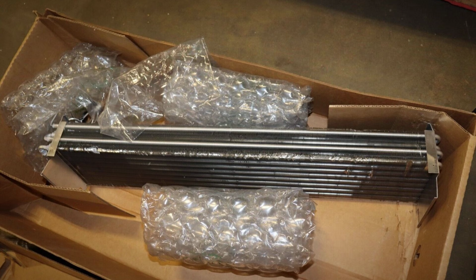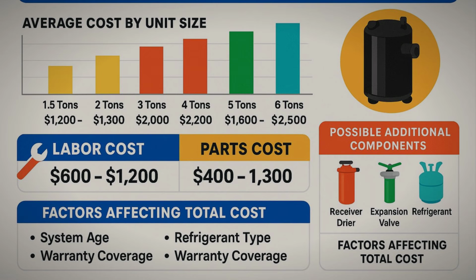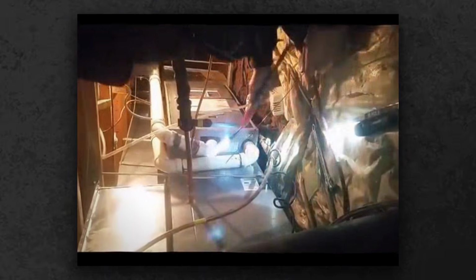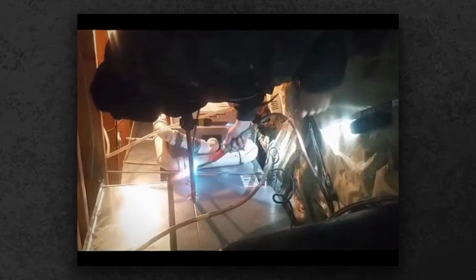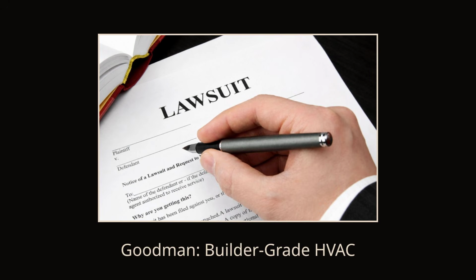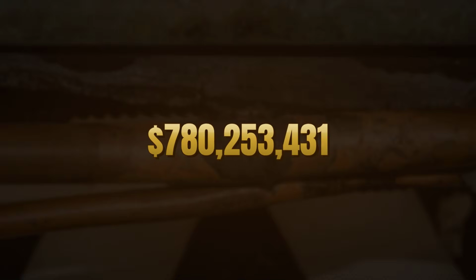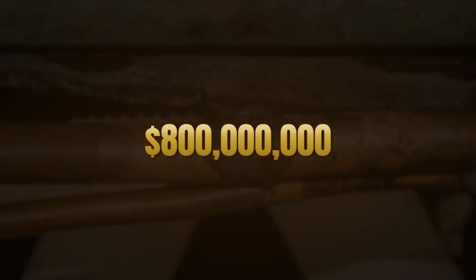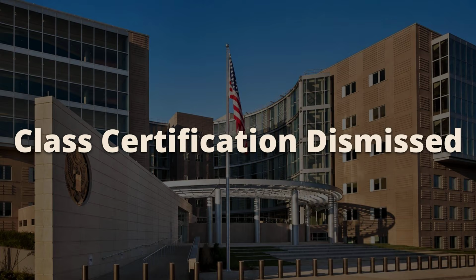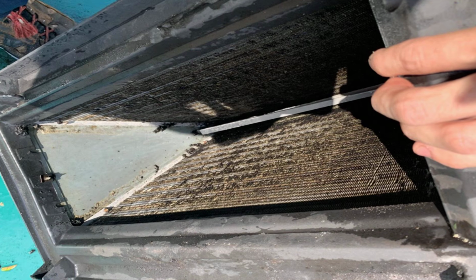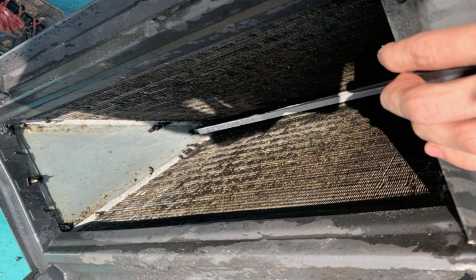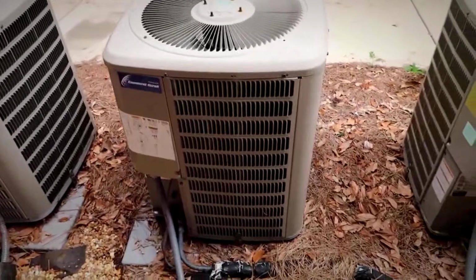Goodman will ship you a new coil under warranty. What they will not cover is the $600 to $1,200 in labor required to tear out the old coil, braze in the replacement, pull a deep vacuum on the line set, and recharge the system with refrigerant. A class action lawsuit alleging this exact defect pattern sought over $800 million in damages. The court ultimately dismissed the class certification, but the core engineering has not fundamentally changed. Technicians see it every single week.